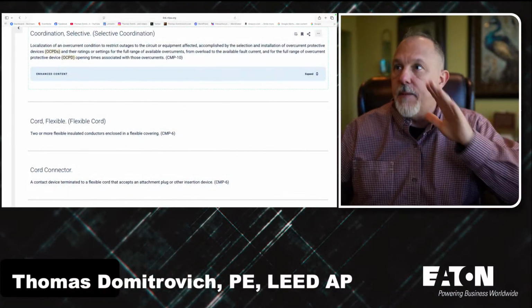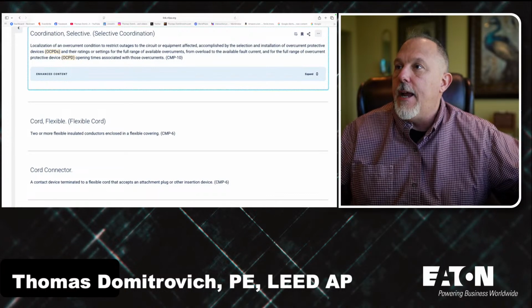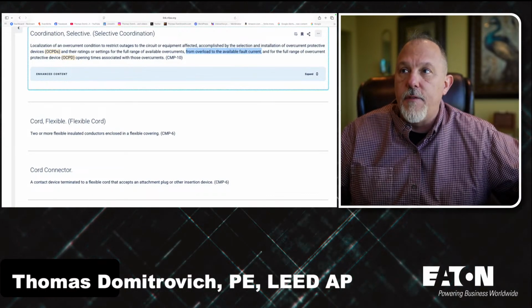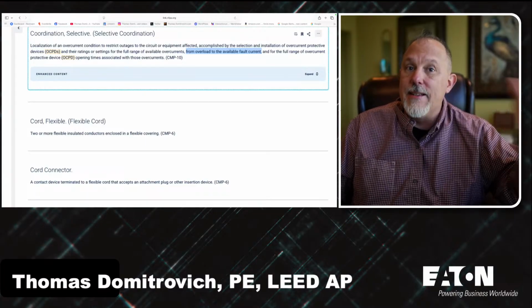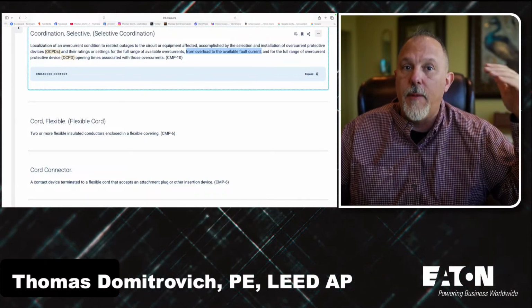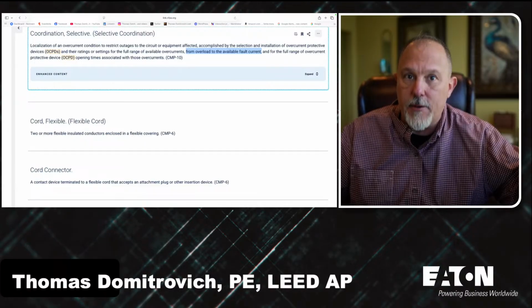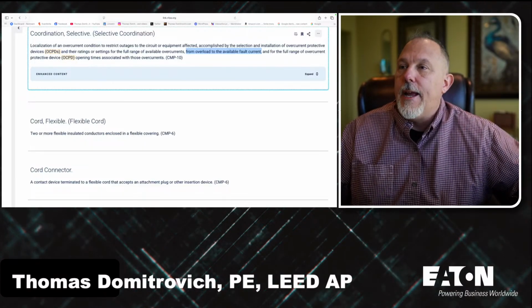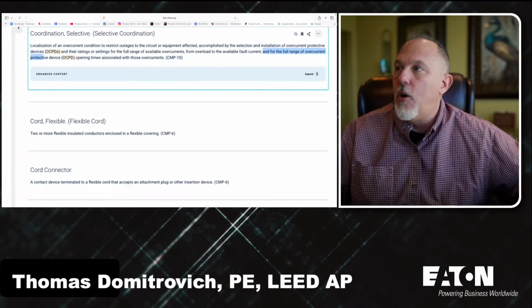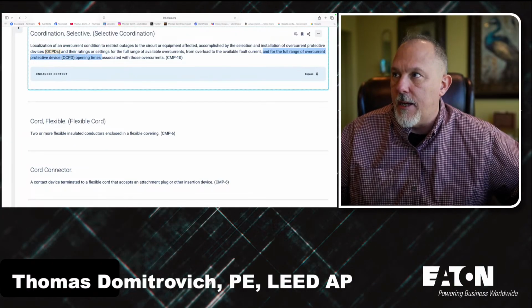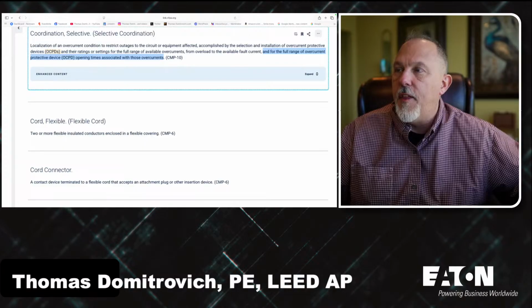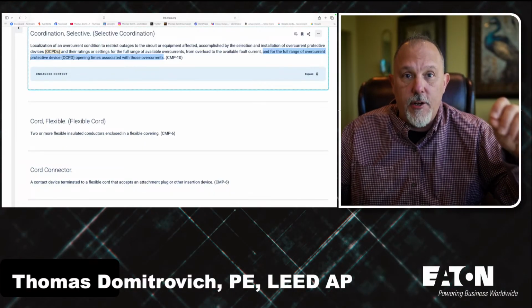For the full range of available overcurrents. We didn't say for the full range of fault currents, we said for the full range of overcurrents. So that's another important piece of this definition. And we go from overload to the available fault current. Now, available fault current is another defined term. It's the maximum amount of fault current at any point in a power distribution system. And it says, and for the full range of overcurrent protective device opening times associated with those overcurrents. And that's the critical function.